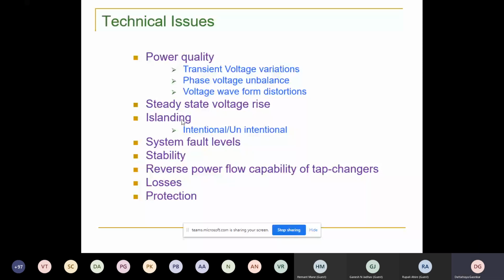Then, as you know, the conventional grid was not designed to have generators on the distribution network. But now, generators are sitting on the distribution network and supplying the fault current. The network may experience that even when there is a fault, the substation end may not see the fault because somebody else supplies the fault current. Okay, stability, of course, in the Indian grid, we do not have that much problem right now because the penetration level is less. But if you think about some of the European networks, they are experiencing the situation.